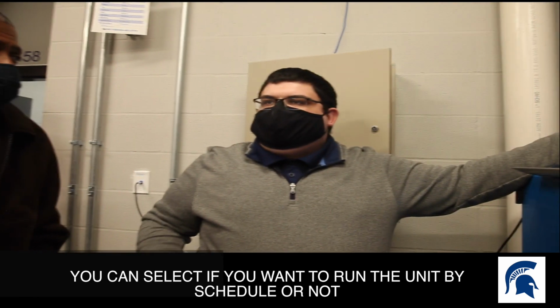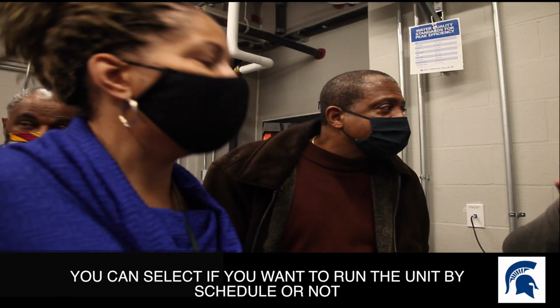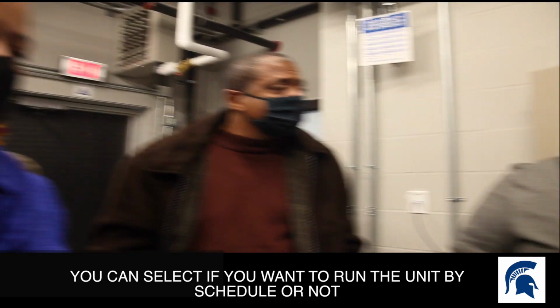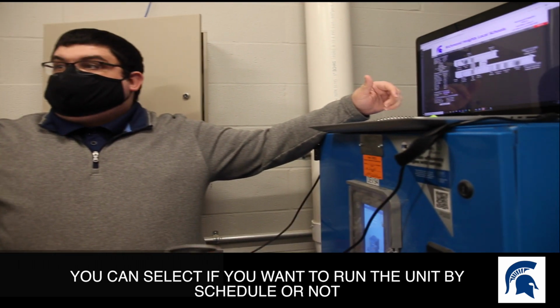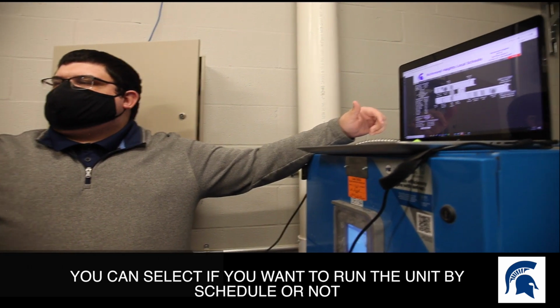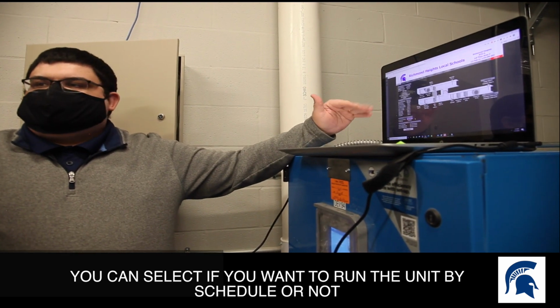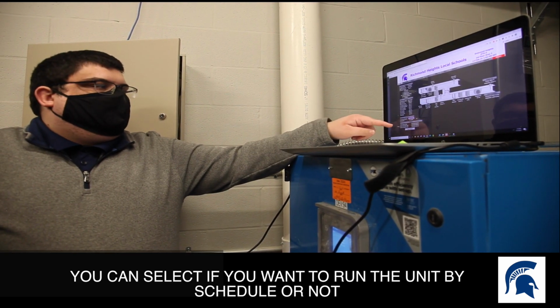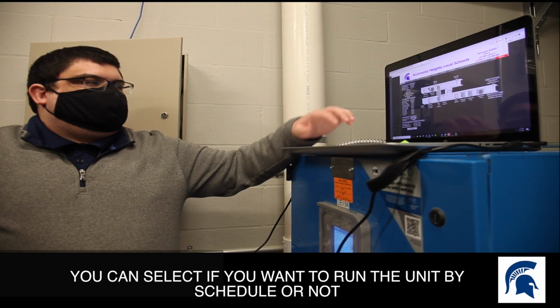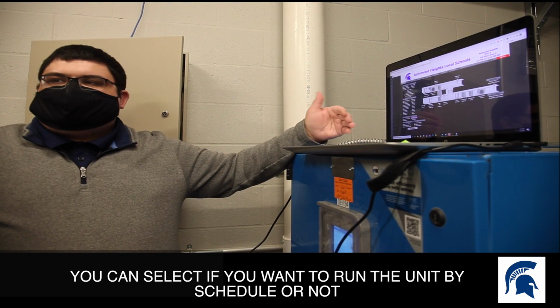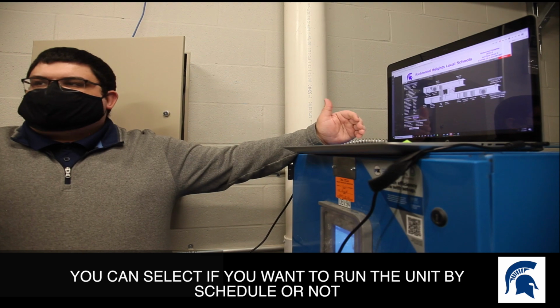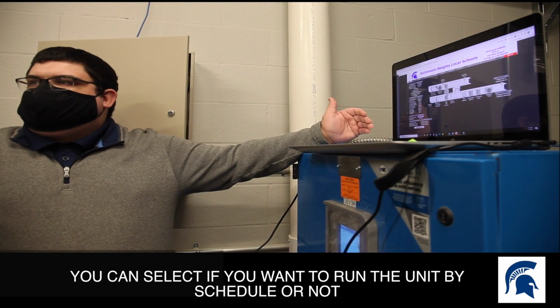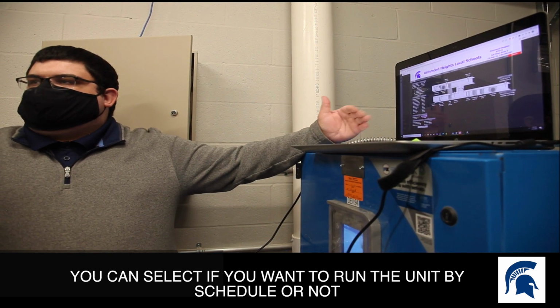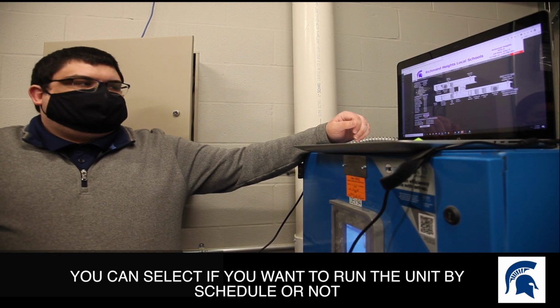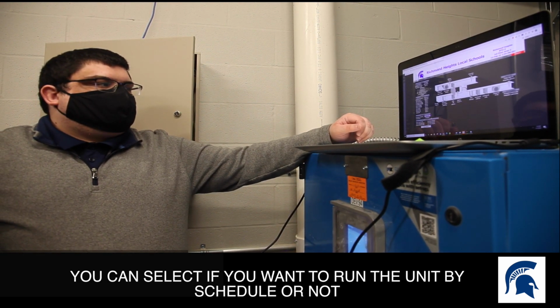BCI. I don't know. That's a company? Yeah, they're who did the temperature control. They have their own schedule configured in there, so it's kind of a fallback. So you can switch between the two. And then this is what the actual command for occupancy is right now. We have a schedule hooked up that's 24/7 right now, so the units are going to run all the time during the super low temperatures we have right now.